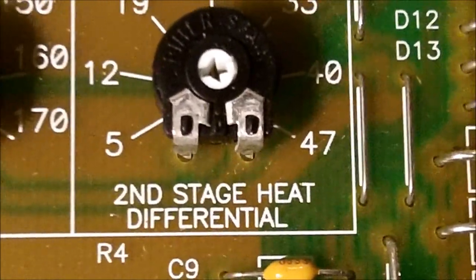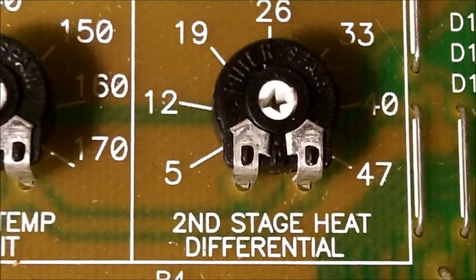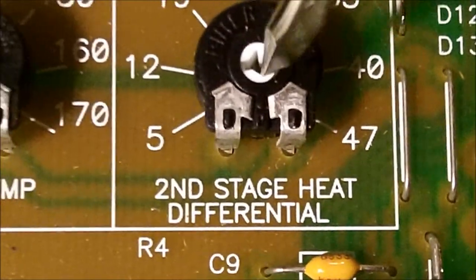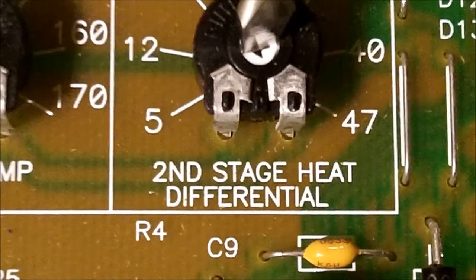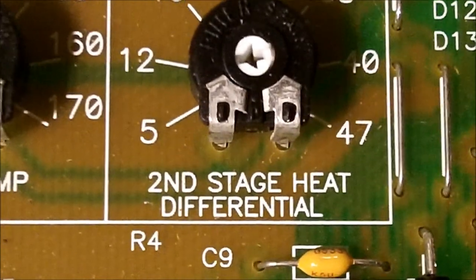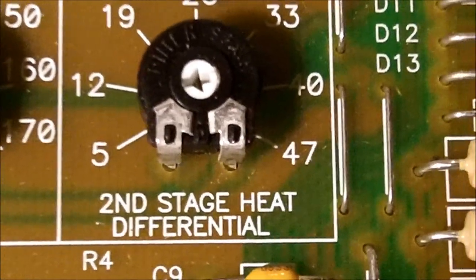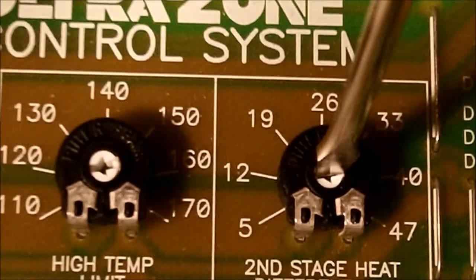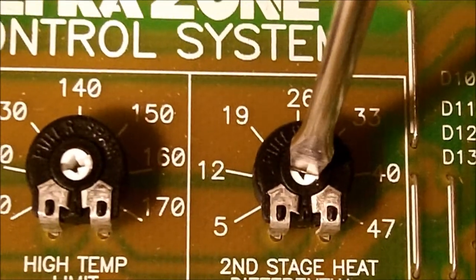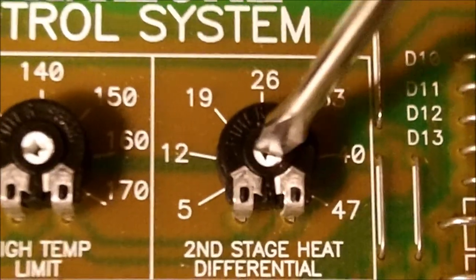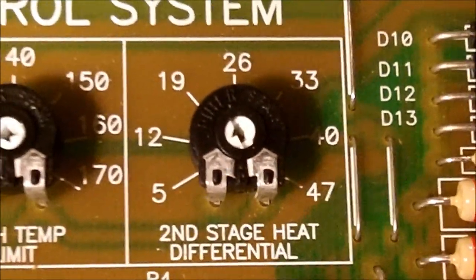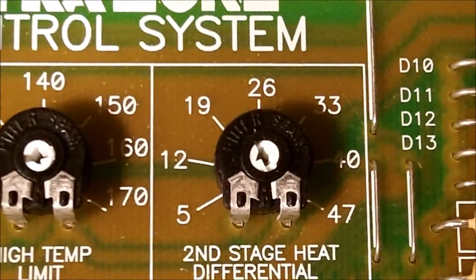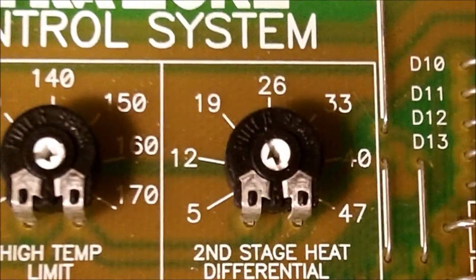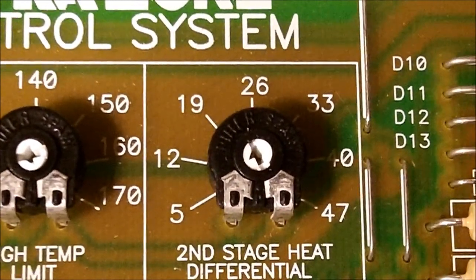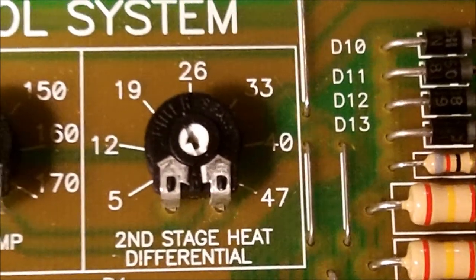Okay, your next one is your second stage heat differentials, meaning if you have this thing set for 140 degrees, then your second stage, if it's in second stage heat, if you have it down to 5, that means if your high limit is set on 140, and that's set on 5, that means it'll go off at 145 degrees. All right, the furnace just came back on. The supply air sensor's cooled down. If you have it set for 12, that's 152 degrees, because your first one's on 140. 19, 26, it just goes up by whatever time you have, and in between there are some temperature settings. Right now it's on 19, so in between 19 and 26, you just kind of got to use your own head on that one.